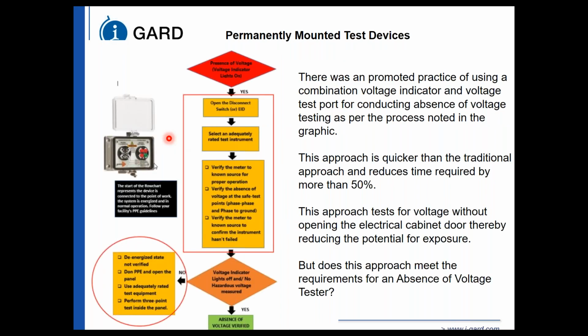So there was a promoted practice of using combination voltage indicators and voltage test ports for conducting absence of voltage tests. You can see by this graphic, the voltage is present, the lights are on. Open the disconnect, select the adequately rated instrument, verify the meter on a known source, verify the absence of voltage by testing phase-to-phase and phase-to-ground, verify the meter is working. And it says here, if you measure no voltage, you have an absence of voltage.